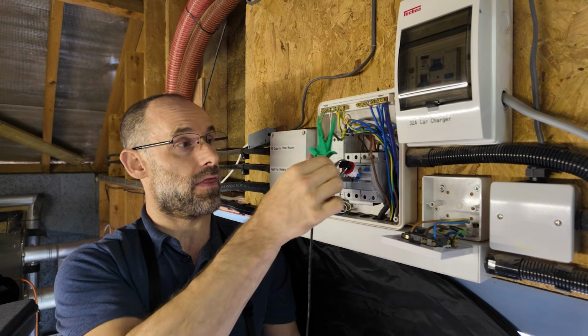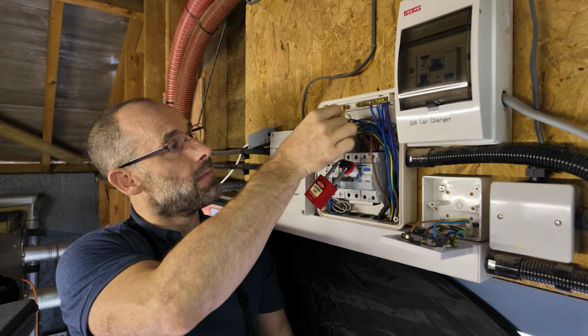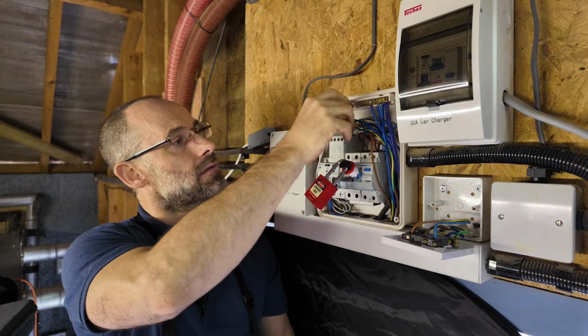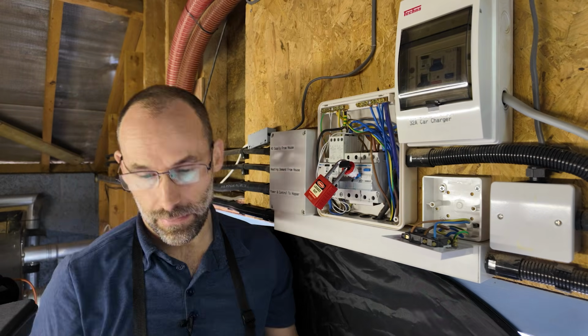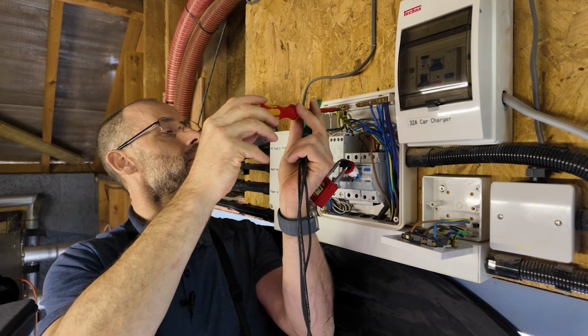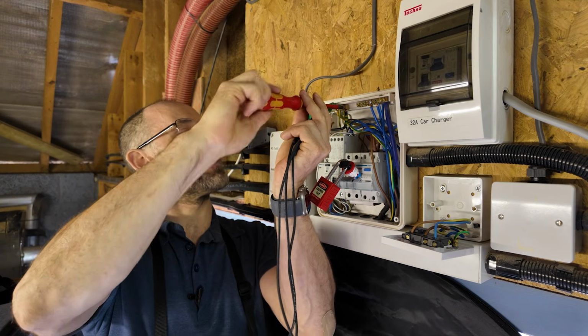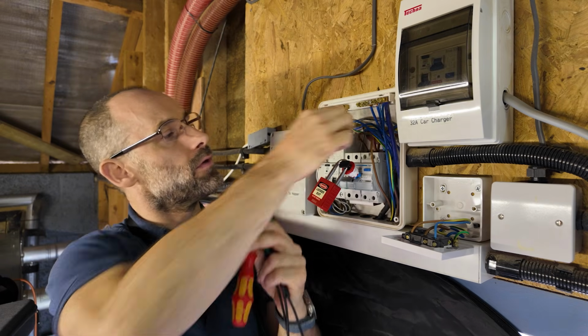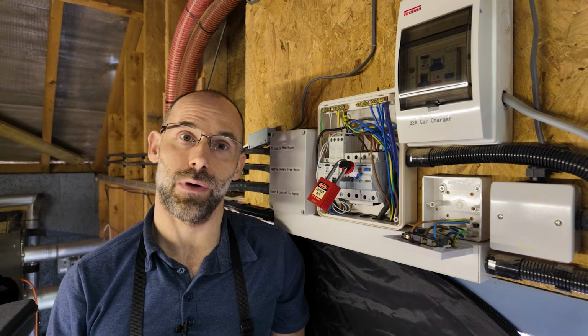At the end of this test, the really important thing I need to do is get this main earthing conductor back in straight away, because clearly we don't want to leave an installation without an intact earth. So let me get that screwed up and tug tested before we do anything else. Okay, on to the next one.